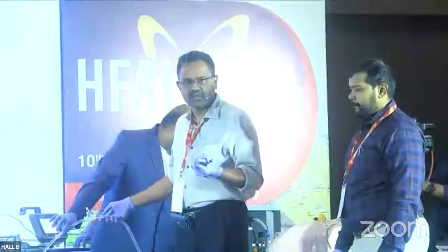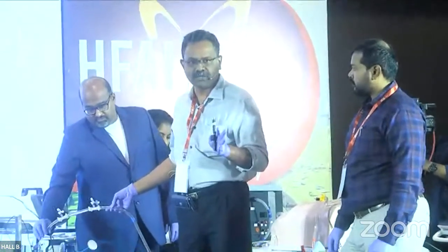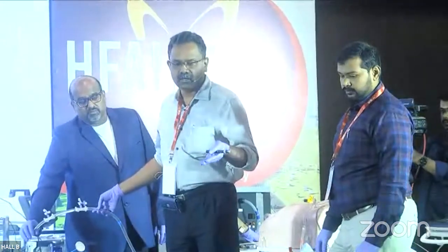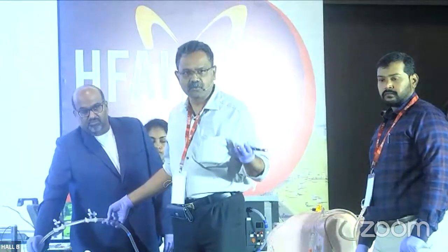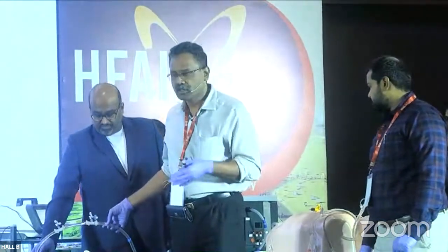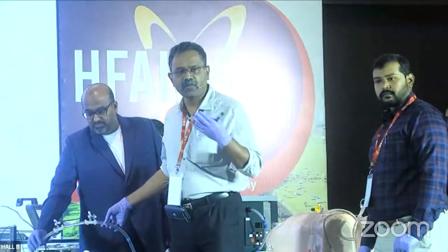This is the blood that comes from the patient to the pump. The pump rotates and sucks the blood, so it will be a negative pressure. Normally around minus 70 is fine. It should be more than minus 70, like minus 50 or minus 40. If it goes less than minus 70, like minus 80 or minus 100 or minus 110, then there will be chattering of the blood, and also a lot of hemolysis, and you can't maintain the flow. So that pressure should be maintained above minus 70, right?